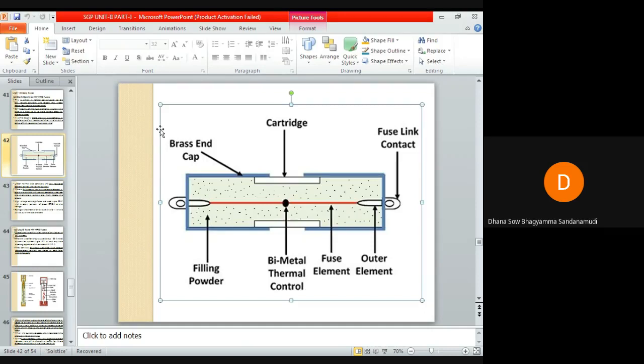Some designs employ a fuse element wound in the form of a helix. You can see a straight fuse element here, but it will be in the form of a helix so as to avoid the corona effect at higher voltages. So in order to avoid the corona effect at higher voltages, this helical fusing element is provided.